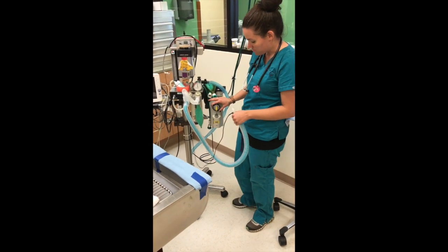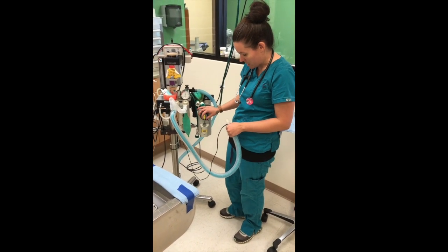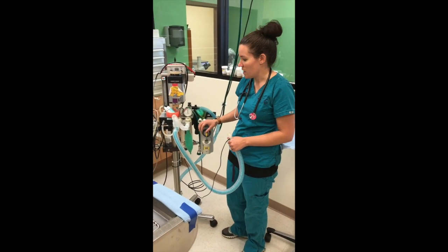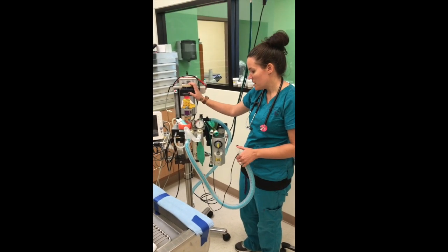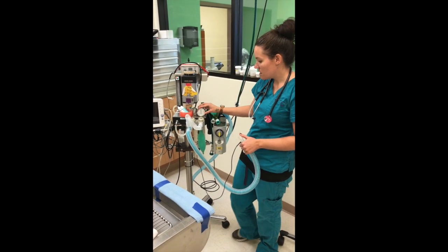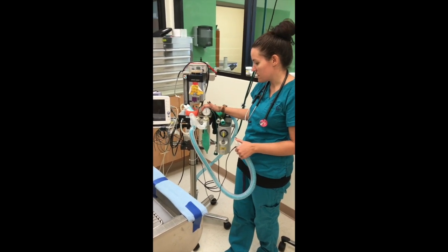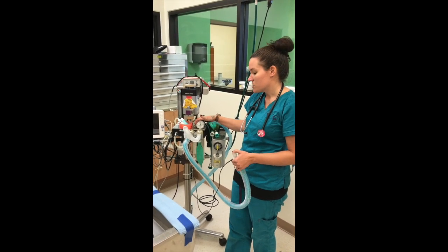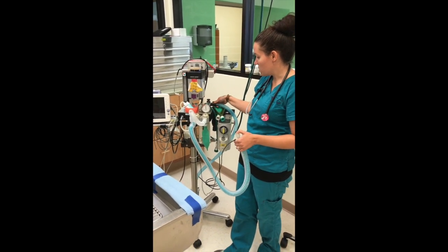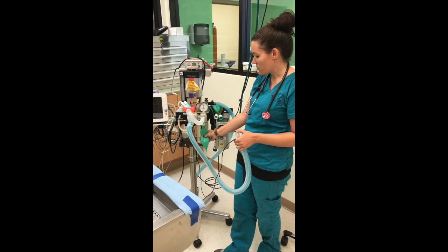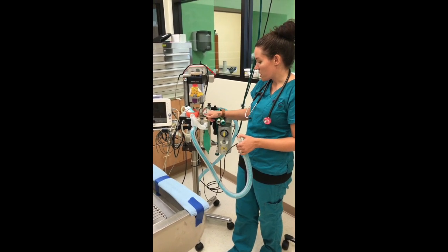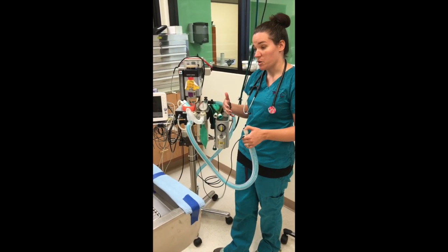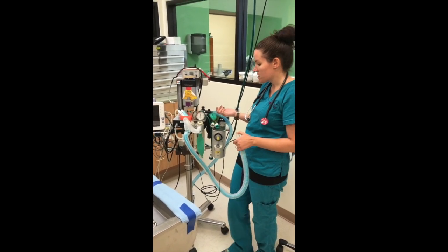We do have a sevoflurane vaporizer here that we can hook into the system. We actually don't use this very often. We primarily use our isoflurane. This is our pressure manometer. It tells us how much pressure is on the system at any given time. When we're giving a breath to a patient, we're holding off our pop-off valve, squeezing our reservoir bag, and you don't ever want to go above 20 centimeters of H2O because that would be too much pressure on the lungs. So we're going to go ahead and do a quick pressure test on this.